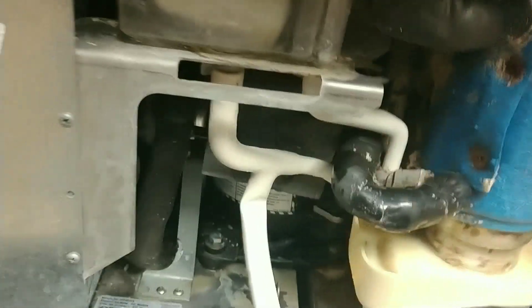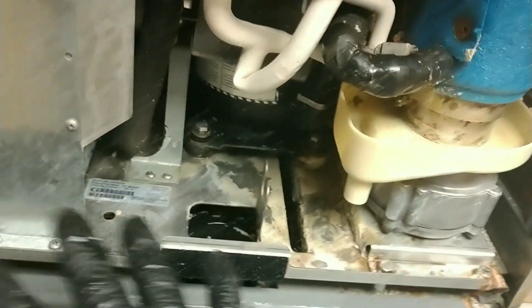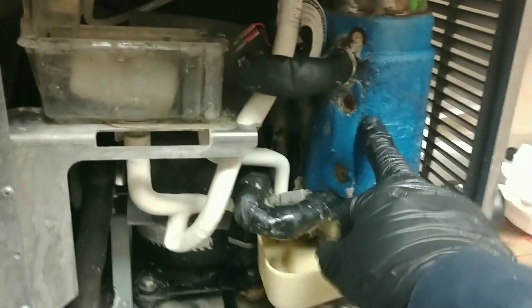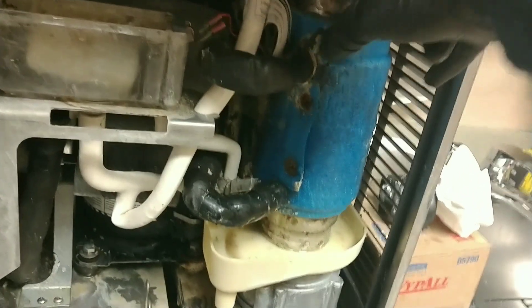While it's rinsing for a third time — which I'm about to start — I'll continue cleaning the outside and make it look nice. Still gonna take this piece off because it's got a lot of scale on it, so we'll clean that as well. For the next 20 to 25 minutes while the cleaner is in there, and then we'll call it a day, get it up and running. If it over-amps again, we'll change the bearings.